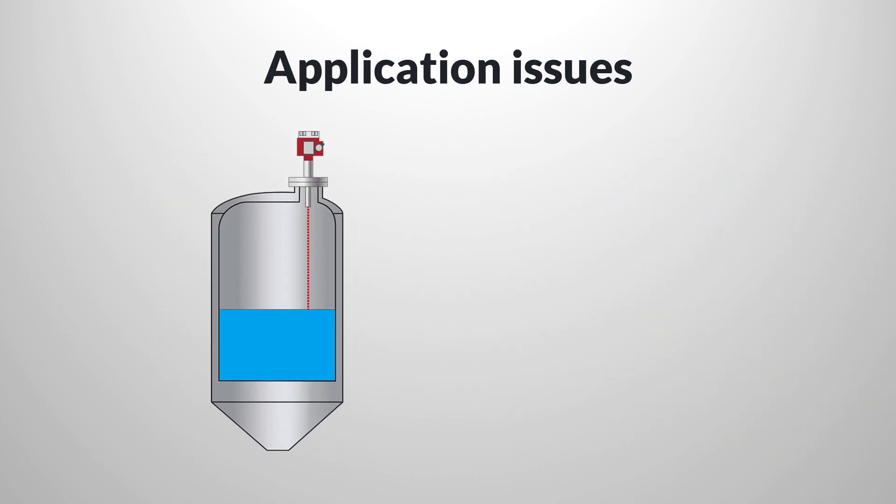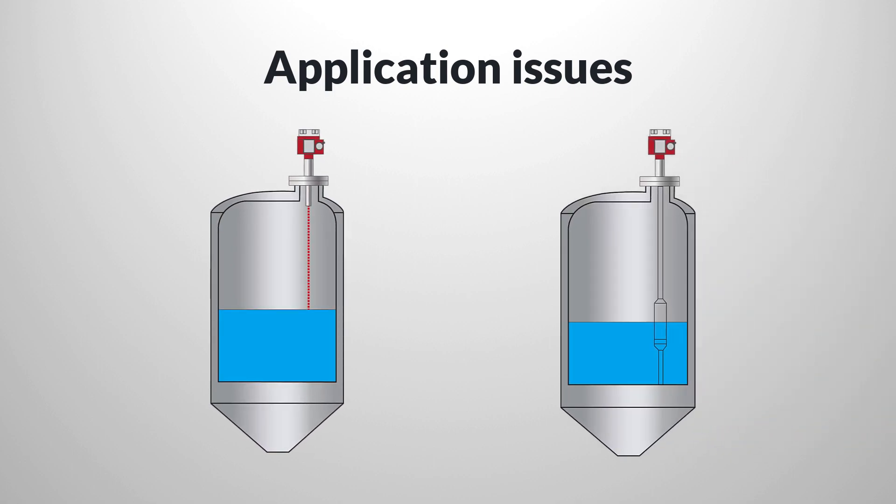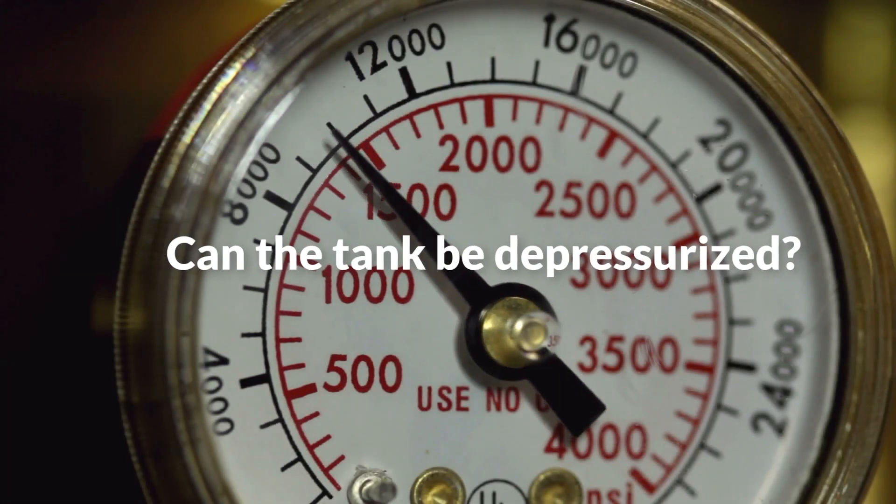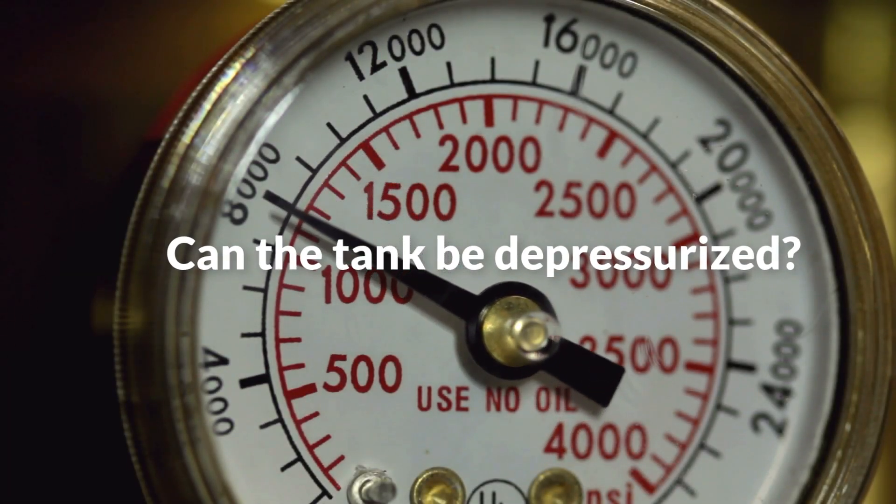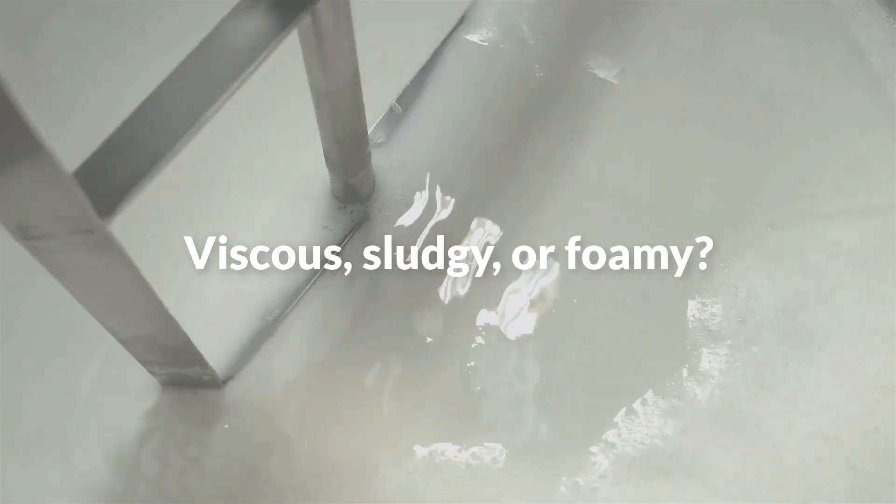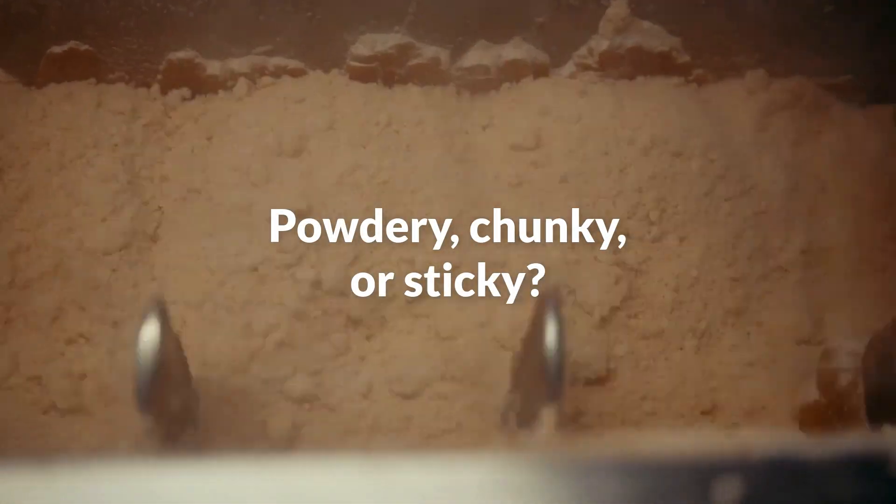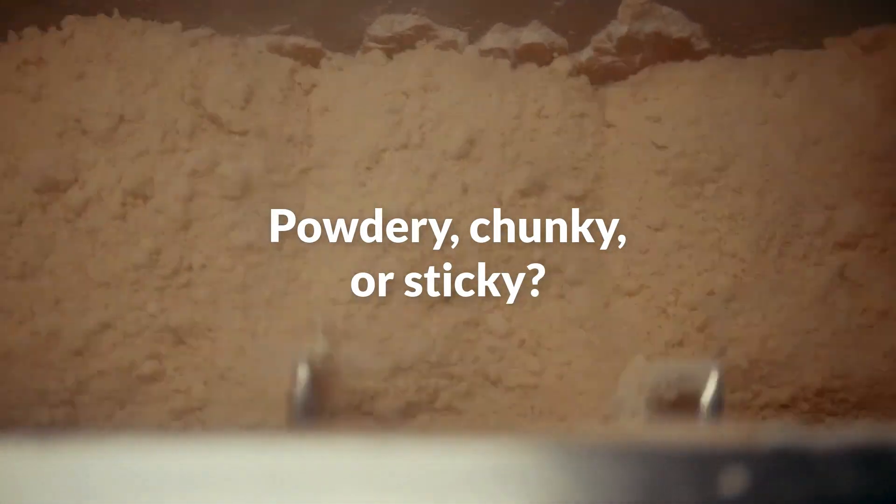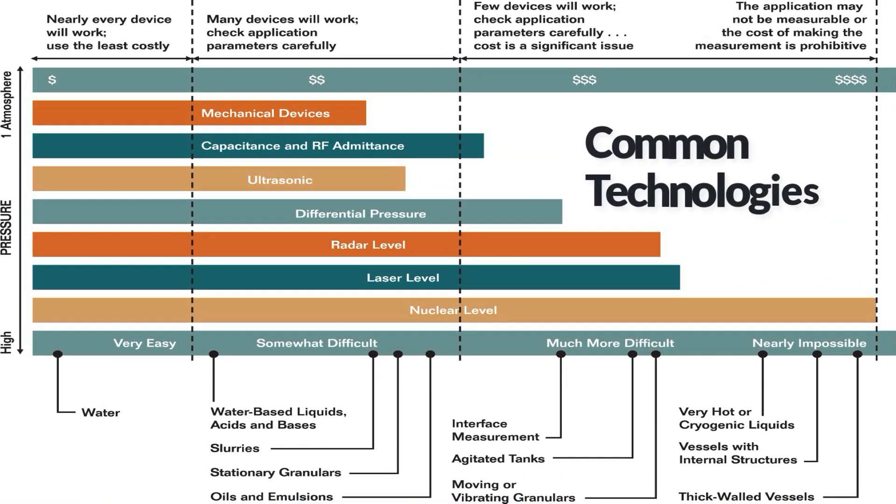Can the sensor come in contact with the process fluid, or must it be located in the vapor space? Is direct measurement of the level needed, or is it acceptable to measure hydrostatic head, which responds to both level and density changes? Can the tank be depressurized or the process shut down to remove or maintain the sensor? Are the tank contents viscous, sludgy, or foamy? Are they powdery, chunky, or sticky?